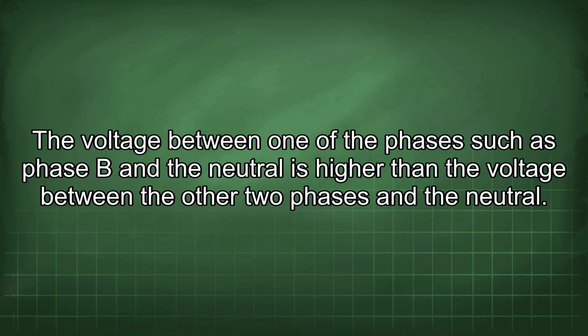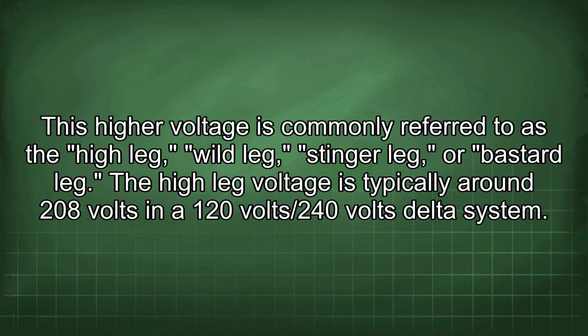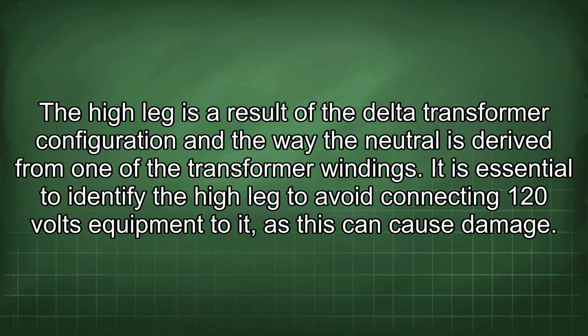The voltage between one of the phases, such as phase B and the neutral, is higher than the voltage between the other two phases and the neutral. This higher voltage is commonly referred to as the high leg, wild leg, stinger leg, or bastard leg. The high leg voltage is typically around 208 volts in a 120V/240 volts delta system. The high leg is a result of the delta transformer configuration and the way the neutral is derived from one of the transformer windings.